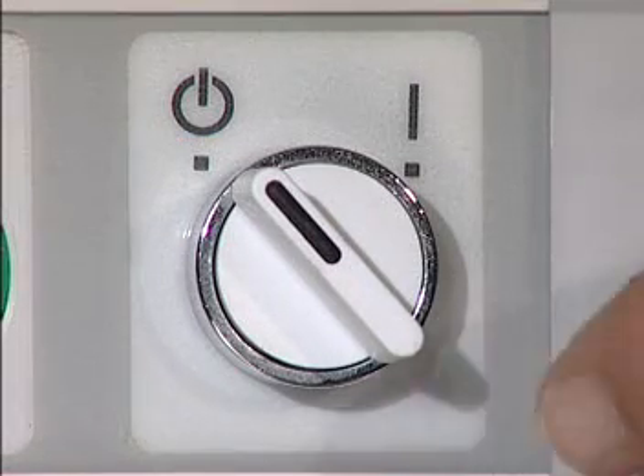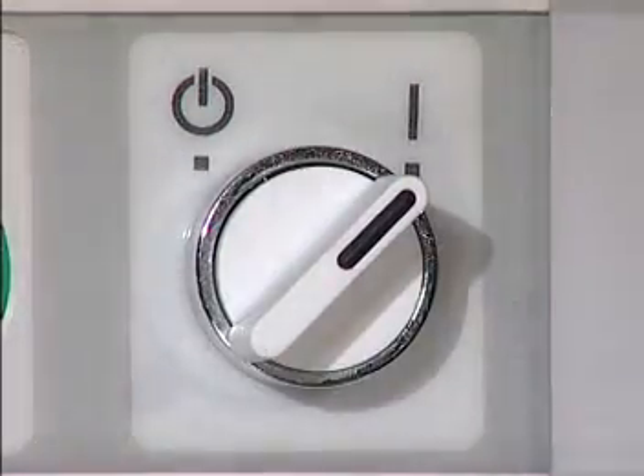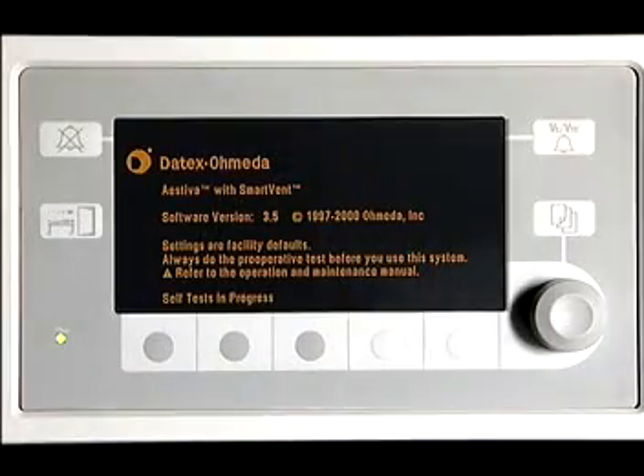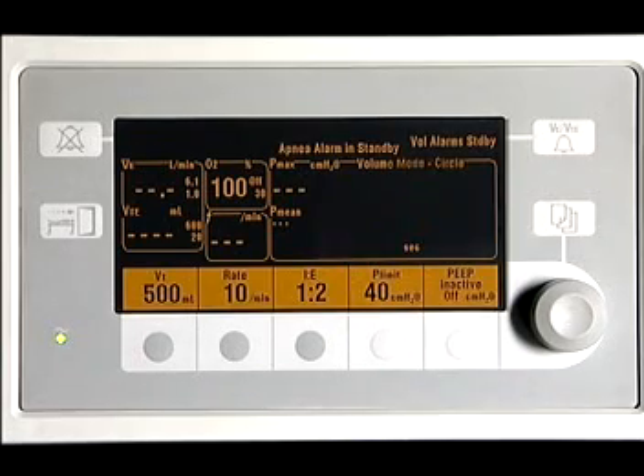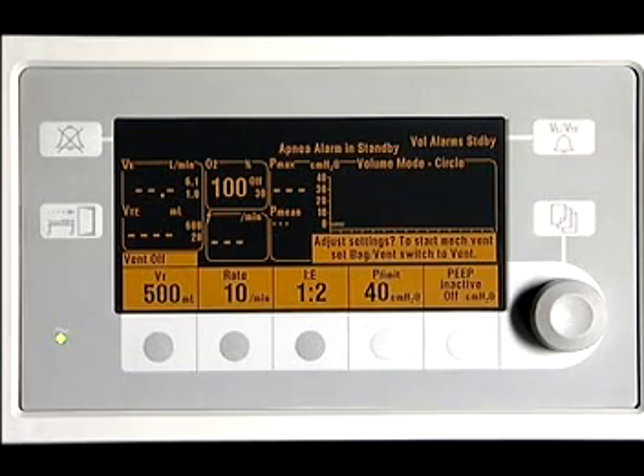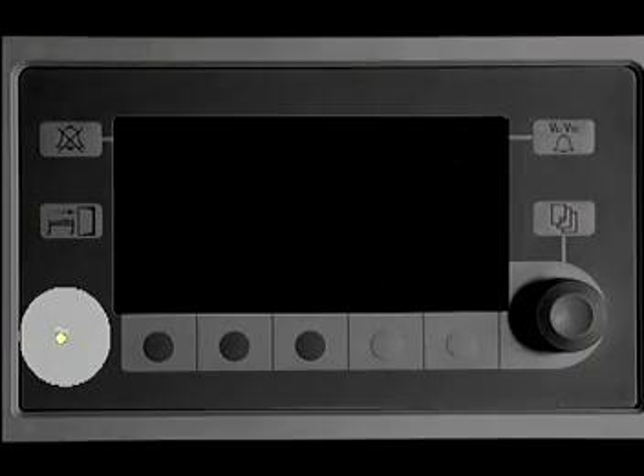single alarm tone. When the power switch is turned on, gases start flowing in the anesthesia machine and the ventilator comes up automatically in manual ventilation mode. An indicator on the lower left corner of the screen shows the presence or lack of mains power. If mains power is lost, the light will extinguish, the screen will indicate on battery, and a periodic tone will highlight the fact that the battery is in use.